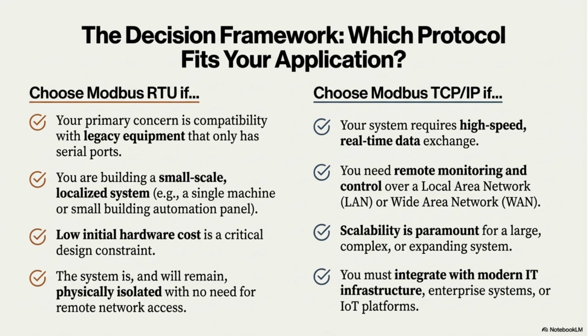Choose Modbus RTU for legacy equipment, small-scale, localized systems, or when low initial cost is key. Choose Modbus TCP/IP for high-speed, real-time data, remote monitoring, high scalability, or integration with modern enterprise IT systems.